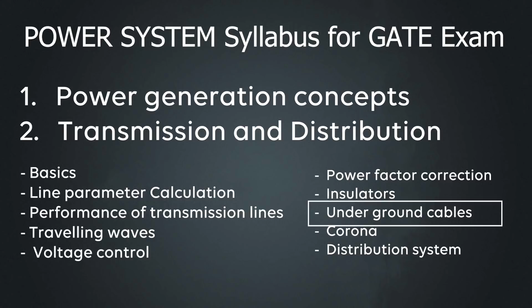Very important here is how electrostatic stress is distributed in the insulation, because by looking at electrostatic stress we can see whether the cable insulation can withstand it, or design the cable to withstand that stress. So electrostatic stress calculations are very important.